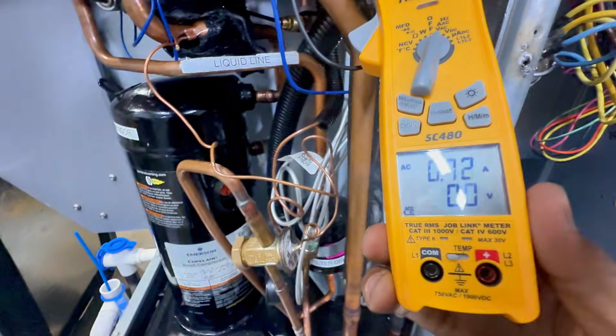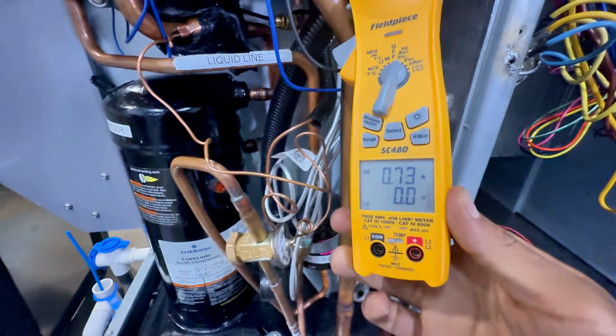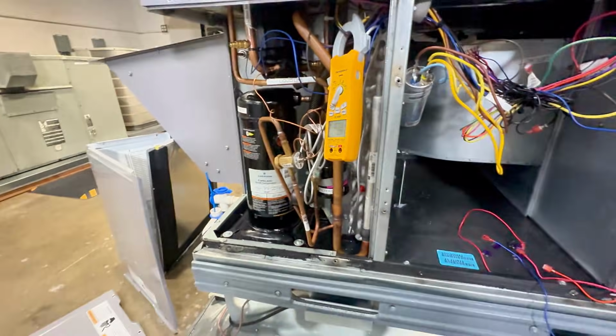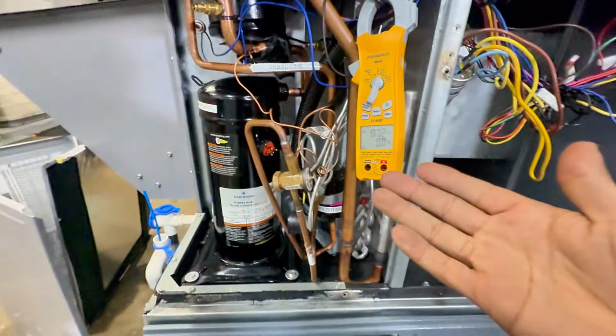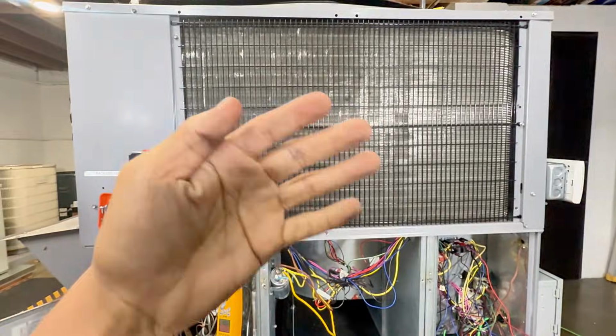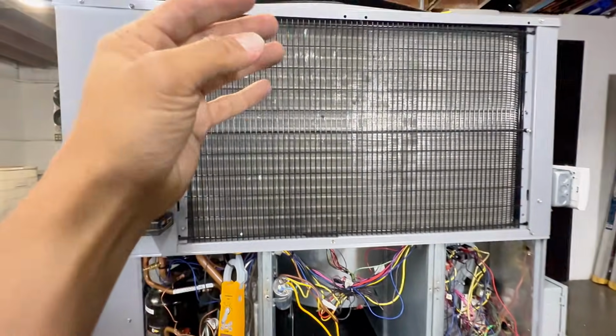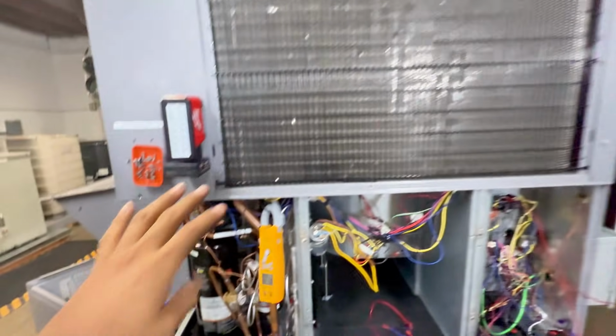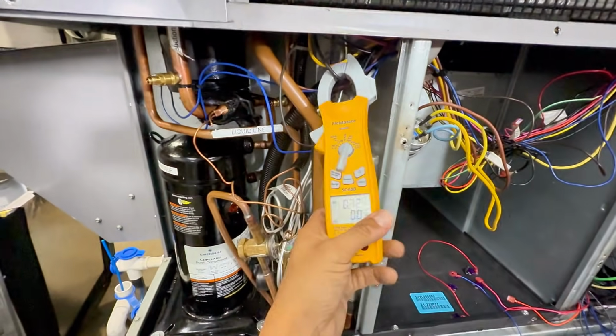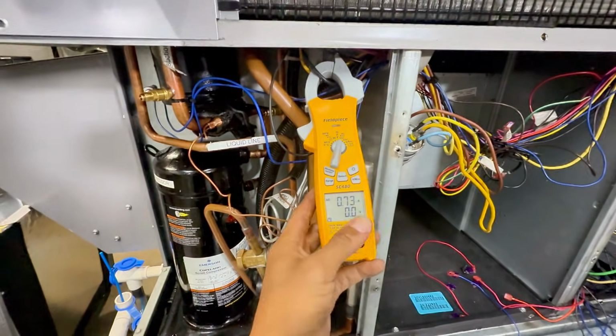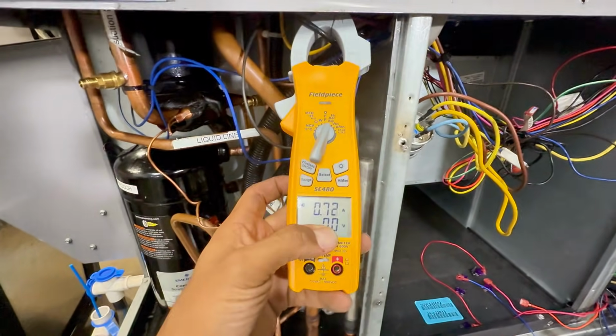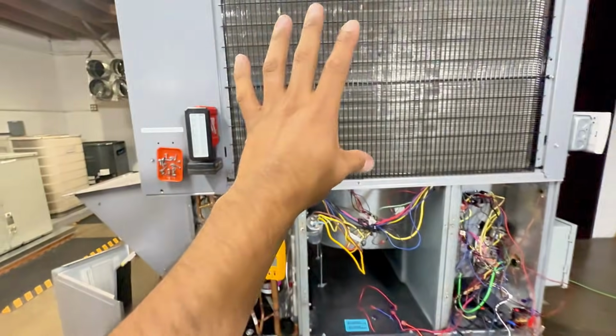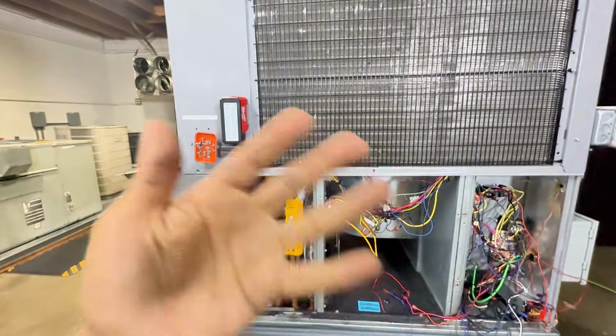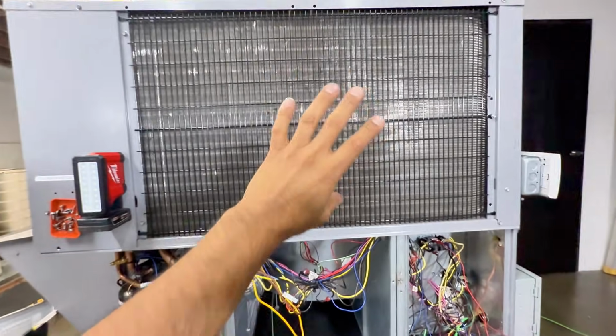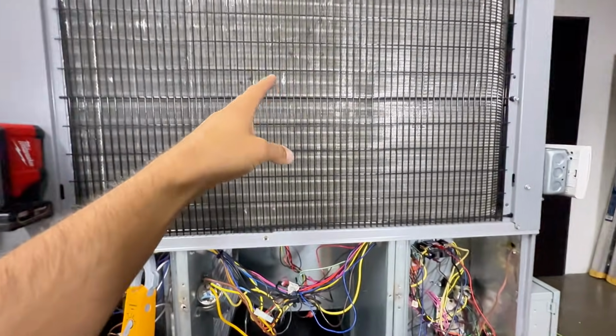It went from 0.64 to 0.73. I gained basically 0.10 more. So it's trying to do its job. Now I'm just wasting energy because I didn't clean my condenser, right? And now to try to make up for the same amount of work that it's intended to do, it's got to put in more energy because it's a dirty condenser. So you see, that amp draw can fluctuate. That is why you want to make sure the condenser is clean.